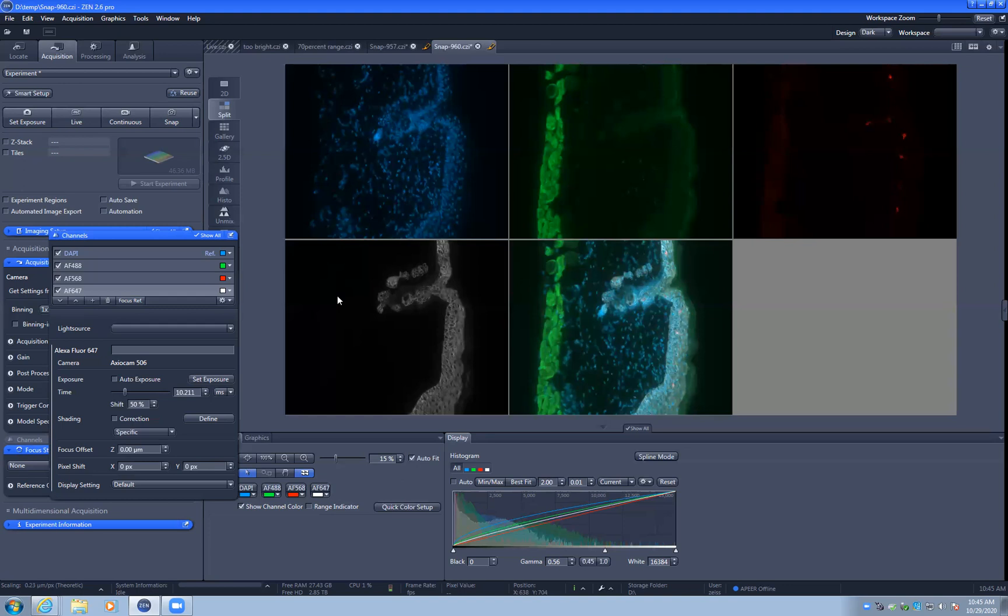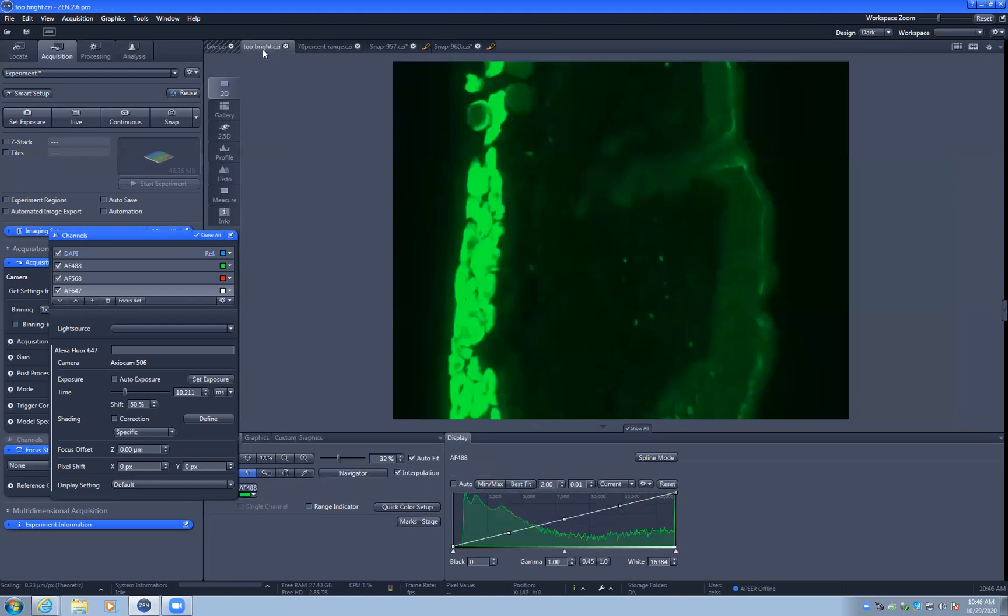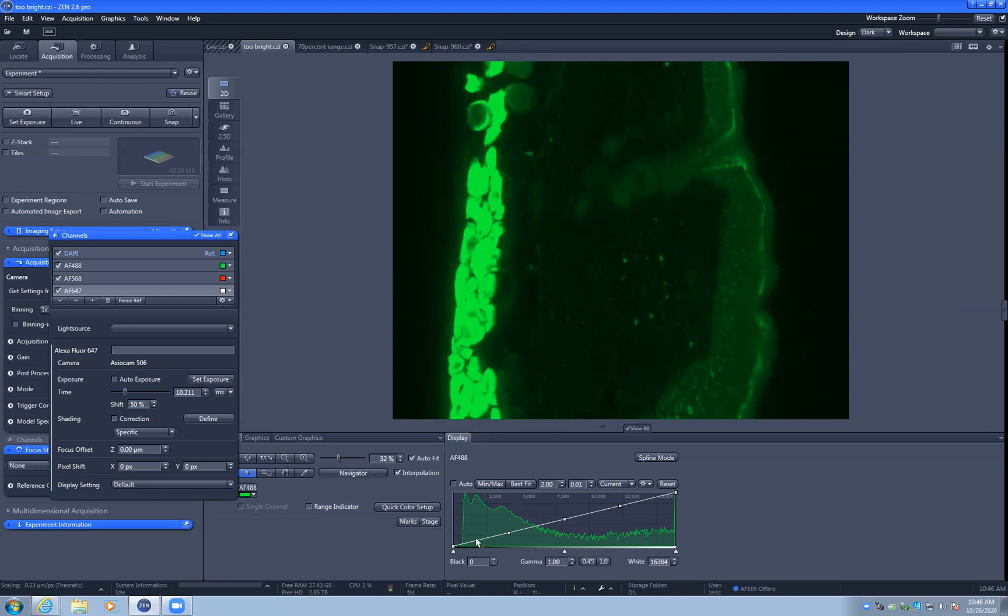Now we can set the exposure for the raw data to not saturate the brightest signal, and the weaker signal will really be in the image, even if we don't see it. So in an image such as this, the structure on the left is way too bright. It's saturated. And there's no way, no matter how we adjust our contrast, to get any information about what's going on. And you can see in our histogram, this peak at the end is showing these saturated pixels. Basically they've all been compressed together at 16,384, and we can't get through that.